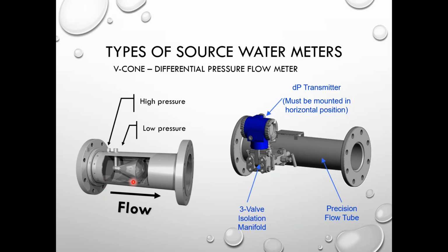And so what this meter allows you to do is to put this in an area that's right off of a pump or right off of what we call a flow disturber. And so when you have flow disturbances, something that conditions the flow is always best. So the prop meters have what we call flow straighteners to try to straighten out the flow and condition it. And this meter has its own cone section that straightens out the flow. And so we could put this in areas where other meters would fail, right?